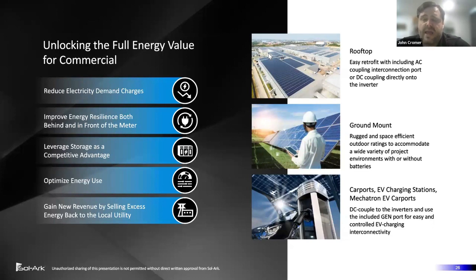Carports are one of my favorite applications in the industry, commercial applications for our battery line with our hybrid inverters specifically, because we do DC coupling on our inverter. So if you have a solar carport, you can land the solar array directly onto the inverter. And then if you're doing a carport today, you're probably wanting to put EV chargers in that parking lot. Well, that gen port, if you don't have a generator in the parking lot, you're not doing AC coupled solar, you can land the EV charging station onto the gen port.